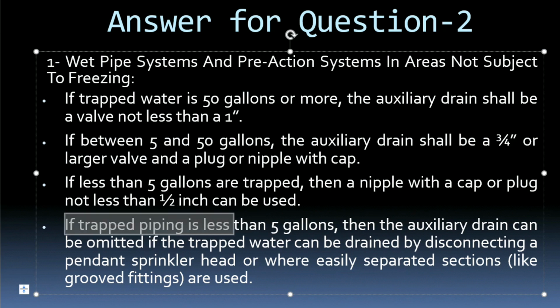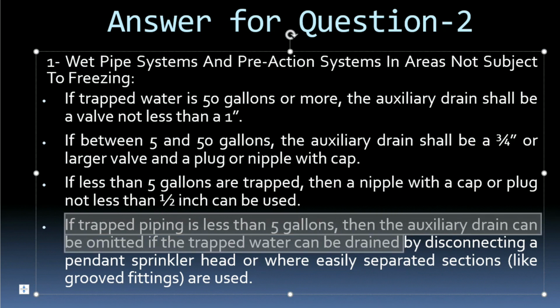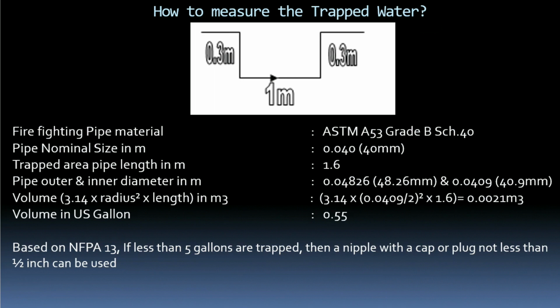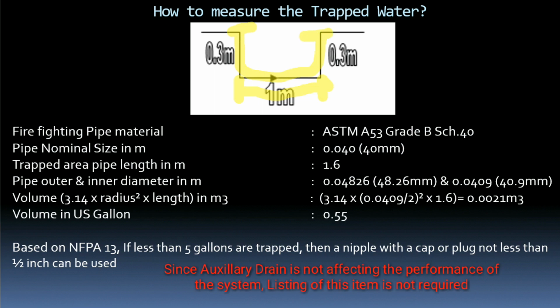If the trapped piping is less than 5 gallons, then the auxiliary drain can be omitted if the trapped water can be drained by disconnecting a pendant sprinkler head. So if this is the case, less than 5 gallons, we can omit the auxiliary drain. But the issue here is how to measure this water gallon limit, from where to where we have to measure. That's the important thing here. If you see this example, we have two options. We can measure the trapped water from here to here, or from here all the way to this point. So there are two options to measure the trapped water.